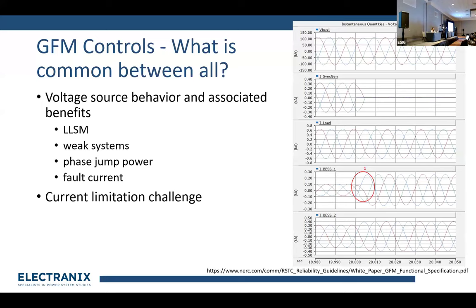A few common constraints all grid forming inverters share: first, the basic definition of grid forming — we want them to look like a voltage phasor in the transient timeframe. That has an associated set of benefits like loss of synchronous machine ride-through, weak system operation, phase jump power, and fast fault current injection. As shown in the recent NERC white paper on grid forming functional specifications, in this situation the grid forming inverter picked up load which was dropped from a tripped synchronous machine, picking it up basically within half a cycle. This is an example of that phase jump characteristic. The other reality for all grid forming controls is that they have to deal with current limits somehow — just because we're acting like a voltage phasor doesn't mean we can ignore all current limits on the device.